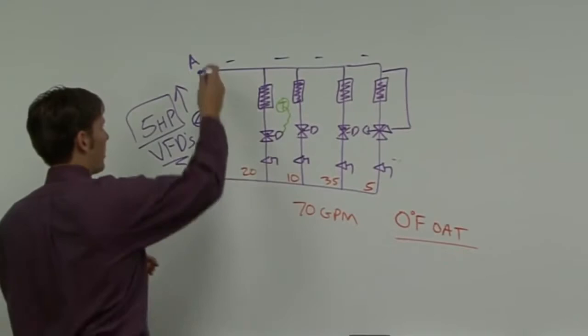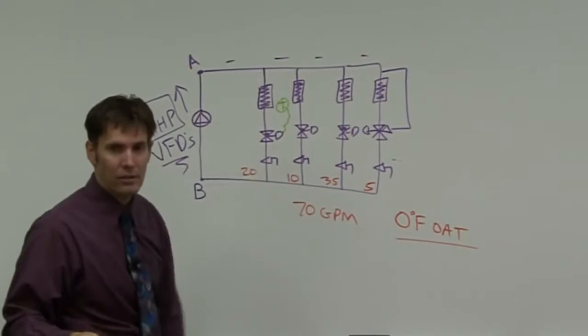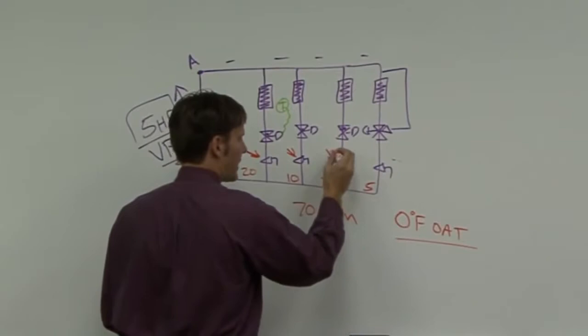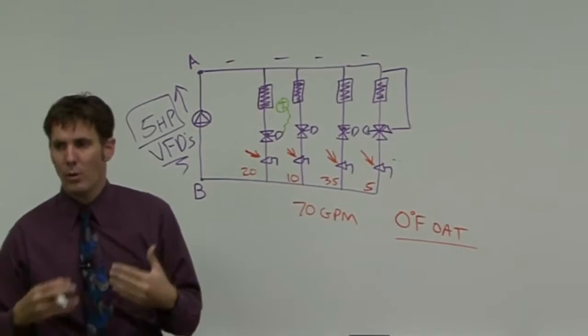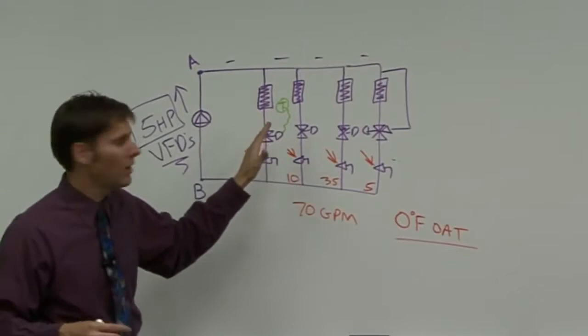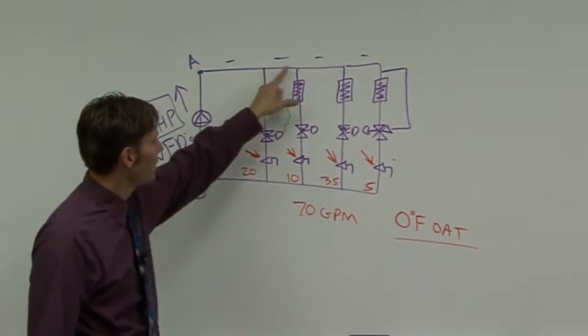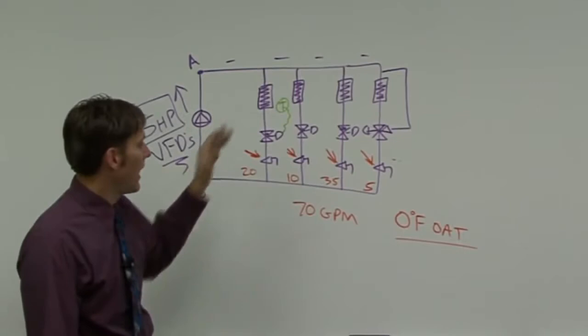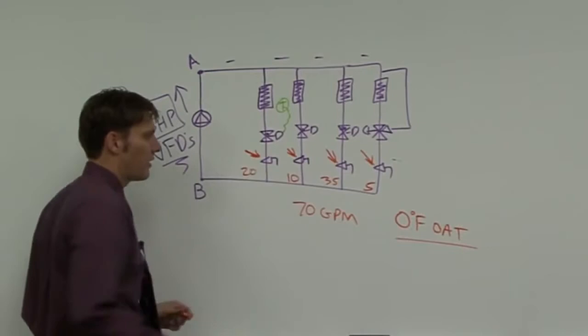How do I know I'll have 20 GPM where I need it? A molecule of water traveling from point A to point B will take the path of least resistance. We have to put in balancing valves and set them so that every path from A to B requires the same effort. In a direct return system, water will flood the nearby circuits and starve the remote ones — that's the nature of the system. We must build in balancing valves to establish equal pressure drops.